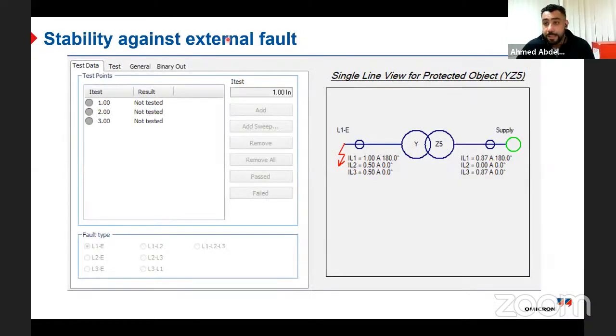So the stability test is a basic test and a very important test. Why? Because, for example, I can't go to test the characteristic if I'm not sure that my transformer is stable or not in case of an external fault, because we have two main requirements for any protection system. The first one is that my system is stable and secure against external fault.